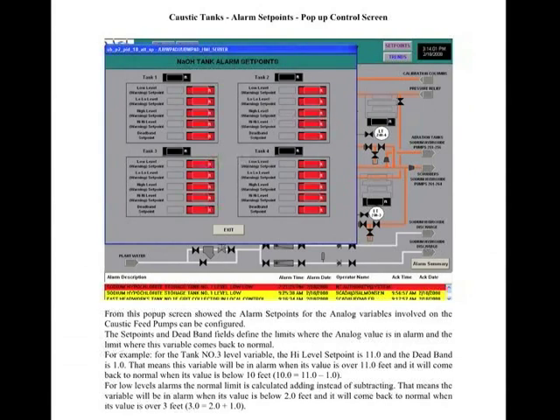You will have high alarm, medium alarm, low alarm, and reorder alarms for your tanks. They're set by set points that usually only the senior operators can change based on their passwords. However, you can look at these screens, you just won't be able to change them. These will tell you when your levels get low and you need to make a phone call to the guy to come and deliver some more. This will tell you when the guy's filling up, when he's near the top of the tank, and prevent him from overflowing and that type of thing.